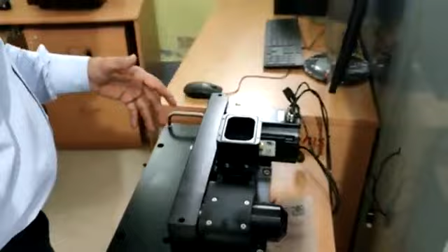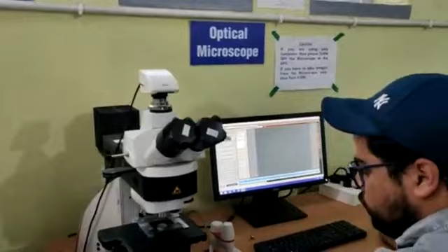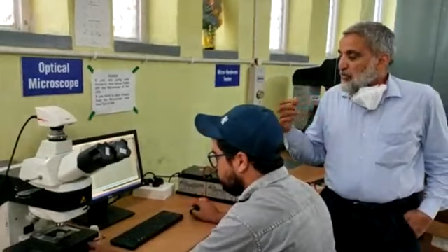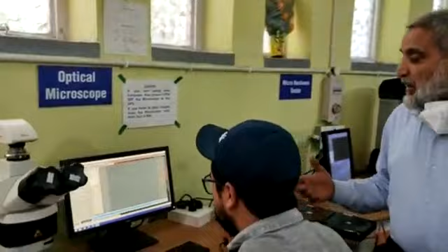This instrument is again used for surface property measurements like hardness, microhardness, Vickers hardness and Rockwell hardness, and this instrument is also automatic. There is a CNC table on this, and this CNC table adjusts itself, and autofocus is obtained. Then we can find the microhardness values with low load as well as a load up to 3 kgs. So we can use it for metals, for composites, and especially for ceramics which have high load capacity. And every tribology lab should have a high-end microscopy, and here we have a high-end microscope on which we can analyze the surface morphology, and we study the microstructure of the samples before and after the test.